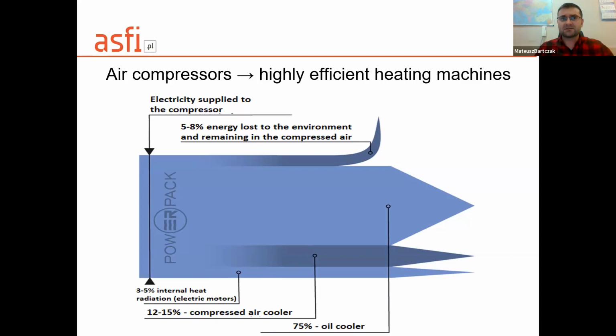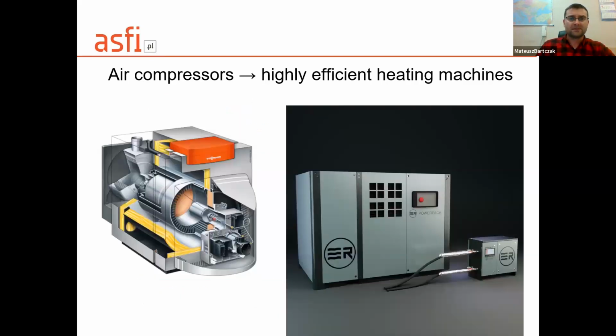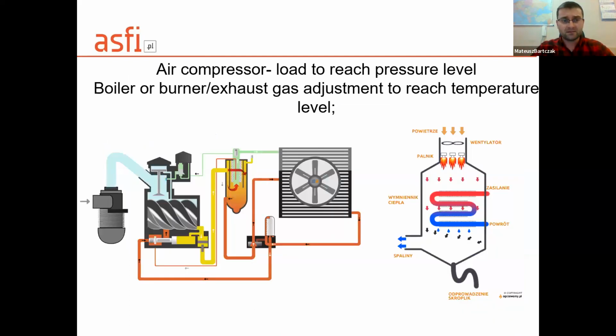The second largest source of available heat is really the compressor air, but we don't talk about it today. Air compressors are high efficiency heating machines. Of course, compressors are not built for that; they are built to reach a pressure level. But despite your initial objection, I'm asking you today during this presentation to accept that the compressor is a highly efficient heating machine. Such a point of view will help you understand the rest of the presentation. Of course, a compressor works to reach a pressure level, while a burner or boiler works to reach a temperature level.